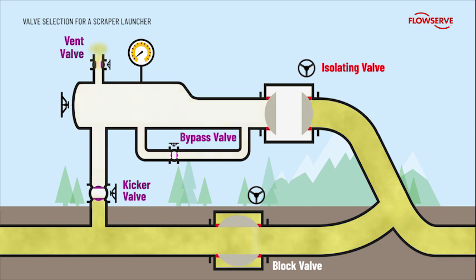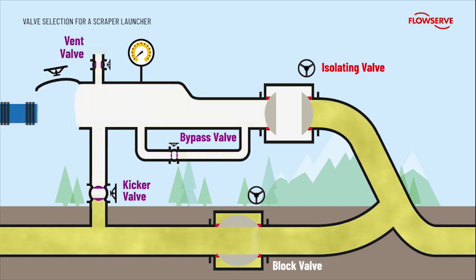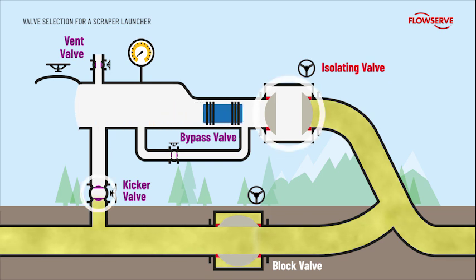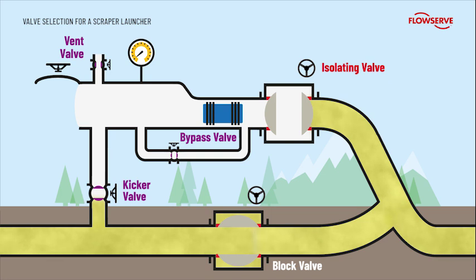When the chamber reaches ambient pressure, the door can be opened and the scraper is put into the launch position. In this phase, it is crucial that the isolating and kicker valves provide a bubble-tight shutoff to isolate the chamber and ensure operator safety, so the correct valve selection is critical.